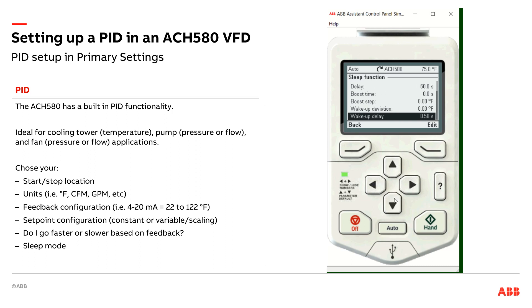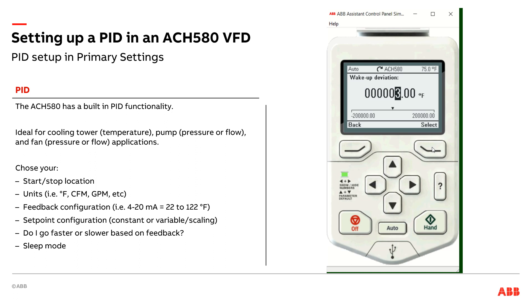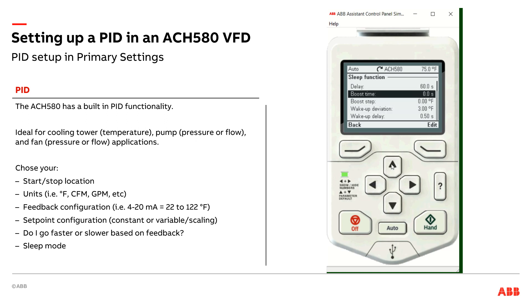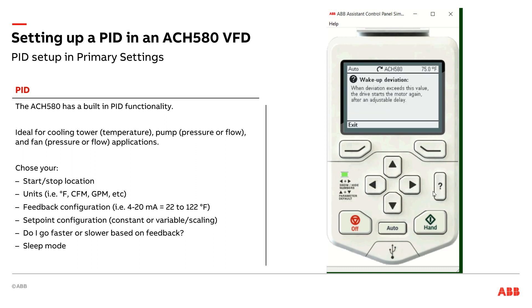Then I look at the wake-up deviation and wake-up time. I basically say when it gets above my set point — my set point is 75 degrees — if it gets three degrees too warm, so that would be 78 degrees for a certain delay time, then it's going to wake back up. I'll also mention the boost time and boost step — more for pumping applications. Before going to sleep, it'll actually speed up a little bit just to pressurize the system, so it can stay asleep a little longer. If you have questions on these, there's always a question mark. For example, wake-up deviation — hit the question mark and it says: when deviation exceeds this value, the drive starts the motor again after an adjustable delay.